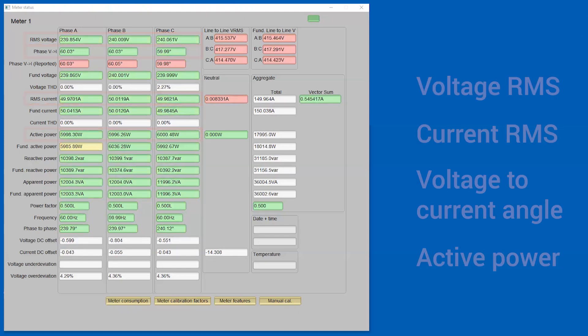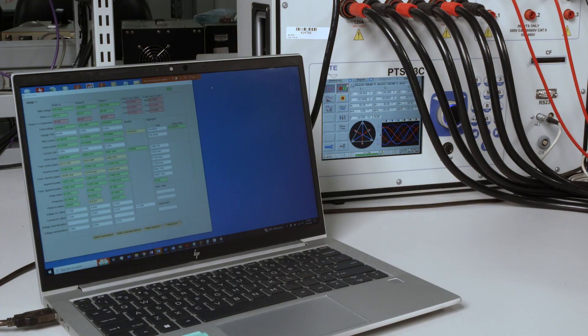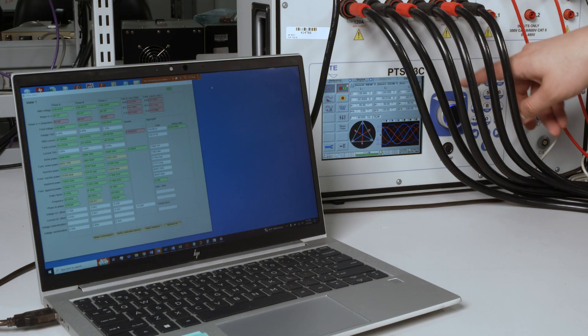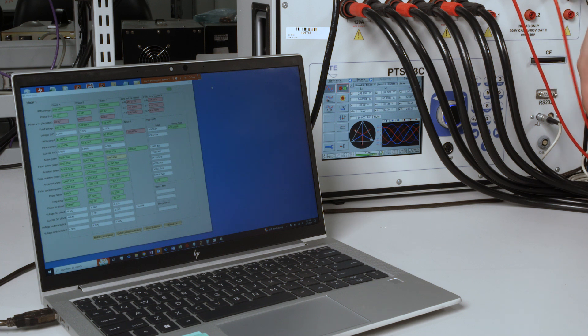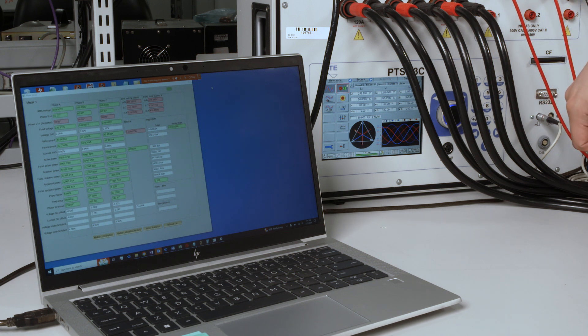Moving back to the MTE, you'll recall that we're feeding the active and reactive pulses back into the test equipment for this next test. Here we can switch tabs to take a look at the accuracy of those outputted pulses. The MTE will read our pulses and give us an average percent error.